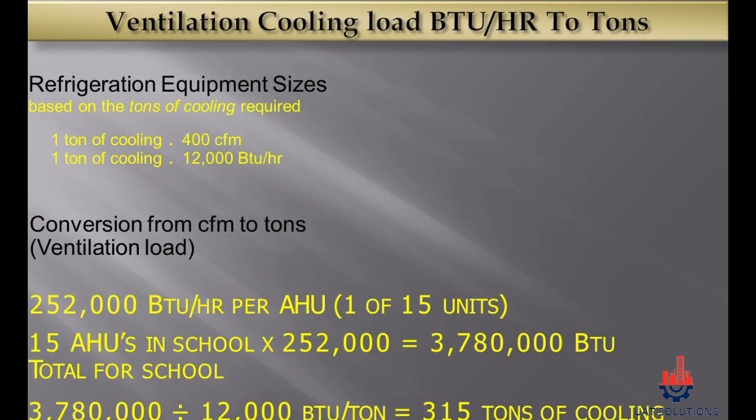Ventilation cooling load for 1 AHU was calculated at 252,000 BTU per hour. With 15 AHUs in the building, total ventilation load is 252,000 multiplied by 15, equaling 3,780,000 BTU per hour. To convert from BTU per hour to tons, divide by 12,000, giving us 315 tons of refrigeration for ventilation cooling only.